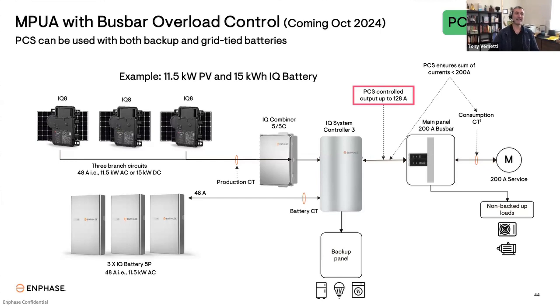With Busbar PCS, the PCS limit can now be as high as 128 amps. This large PV system would likely never be curtailed, as I mentioned before. And here we've got 3 of the IQ Battery 5Ps. They would also be able to output their max current of 48 amps without any issue.